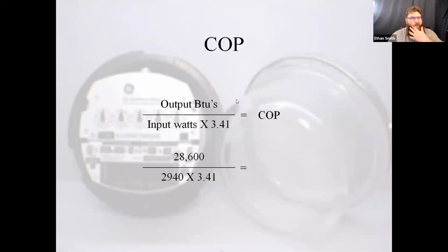Okay, so if we take an example here, I'm outputting 28,600 BTUs, and I'm using 2,940 watts. And we multiply that by 3.41 BTUs per watt, and we come out with a COP of 2.85. Okay, what does that really mean? That means if I were to use the same amount of power to run an electric heater, I'm getting 285% more heat out of my unit than I would running straight electric. So this is a comparison of what you're getting out of the unit versus what you would get out of the unit if you did straight electric. You can think of this as a multiplier. You're 2.85 times more efficient than running straight electric heat with that heat pump at that set of conditions.